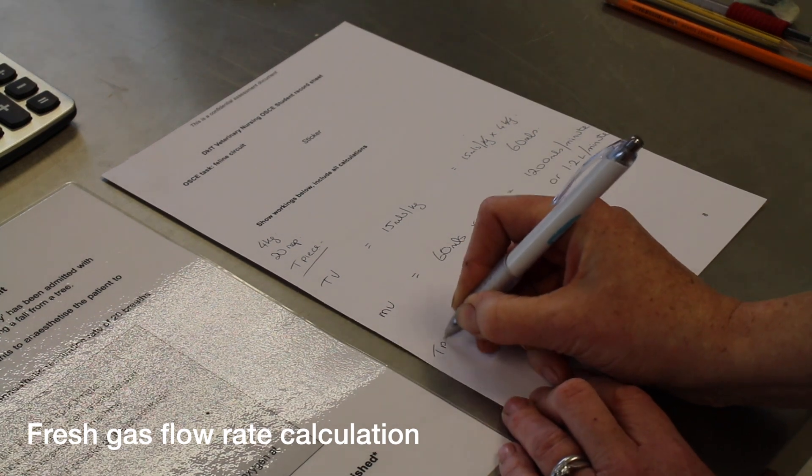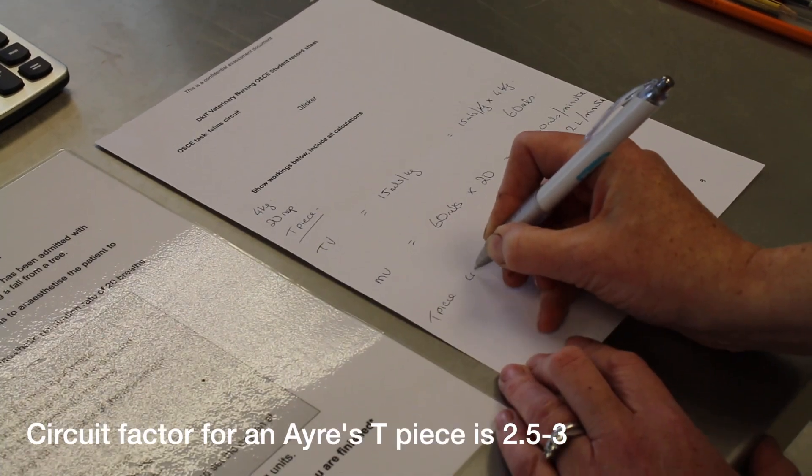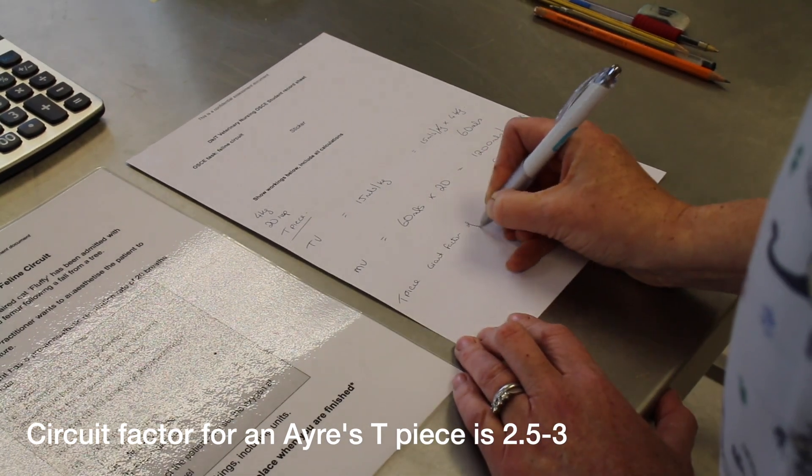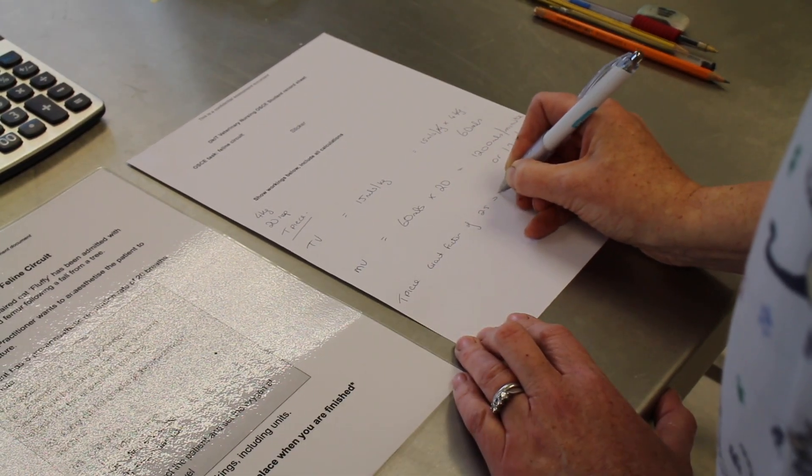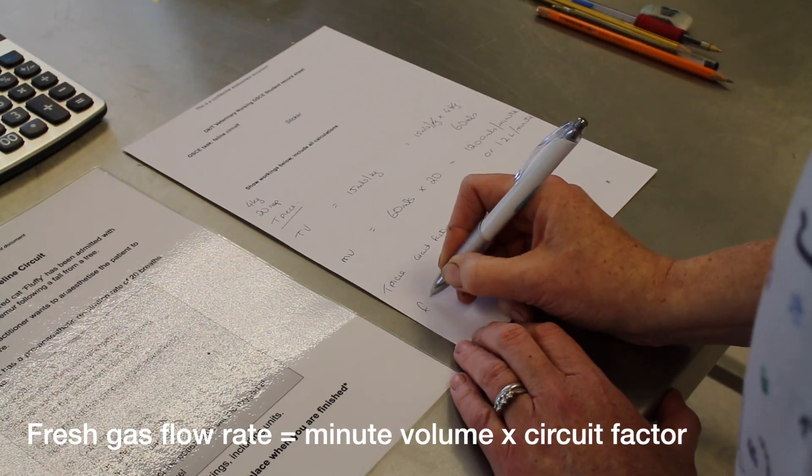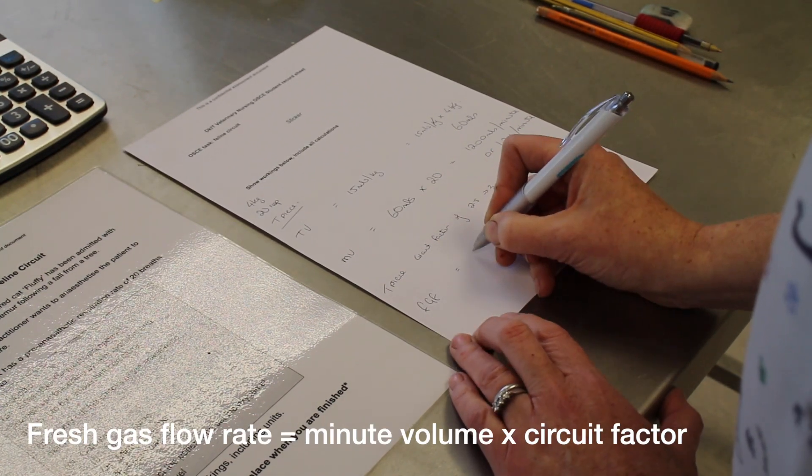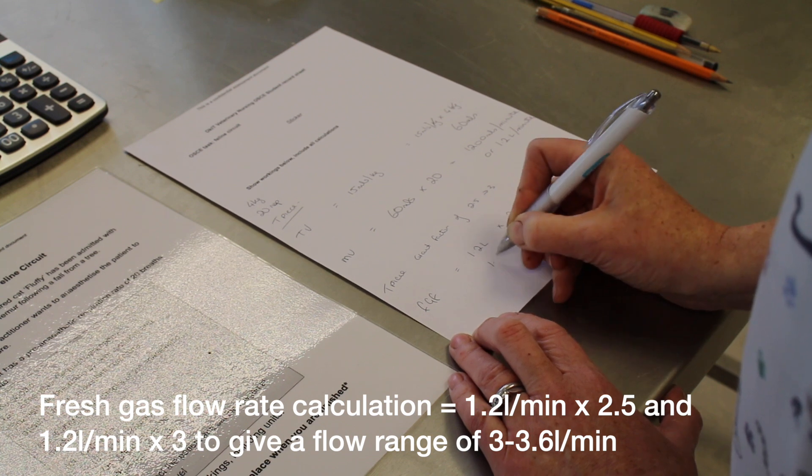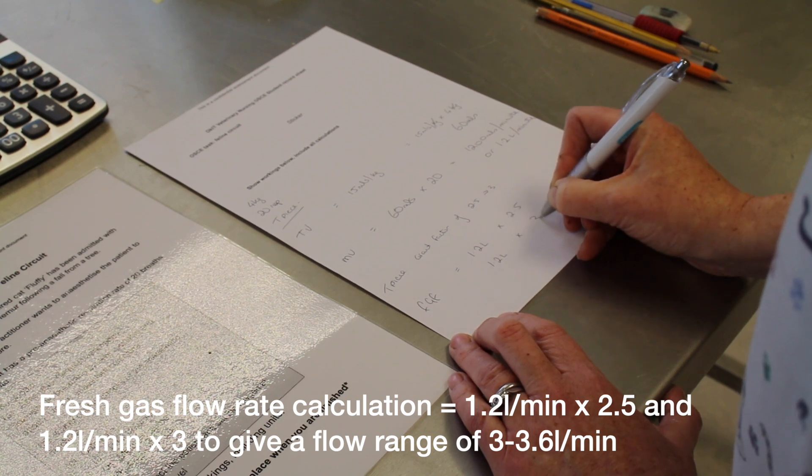So for our T-piece, we have a circuit factor from 2.5 to 3. So our fresh gas flow is 1.2 liters multiplied by 2.5 and 1.2 liters multiplied by 3.